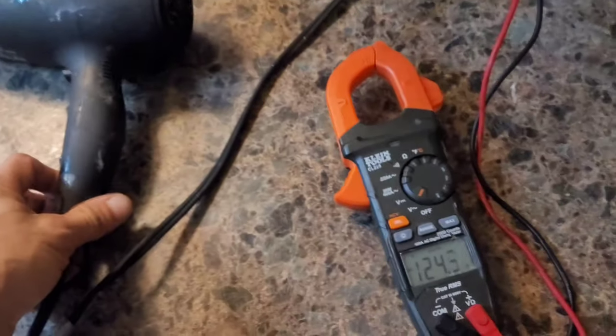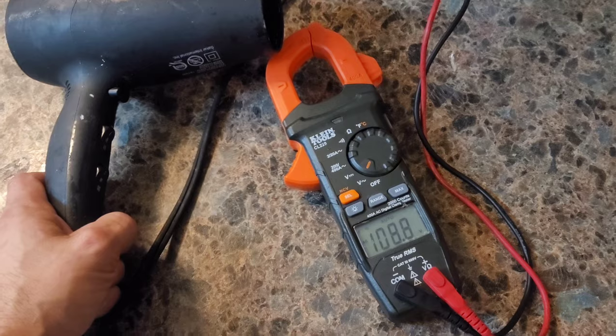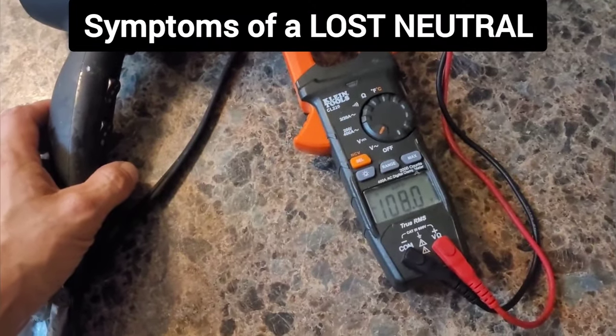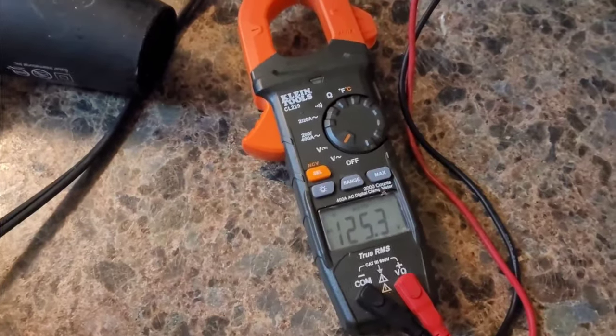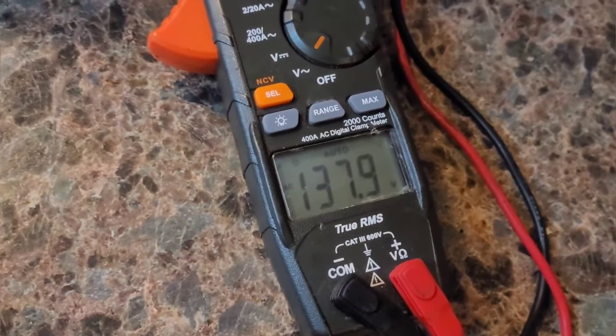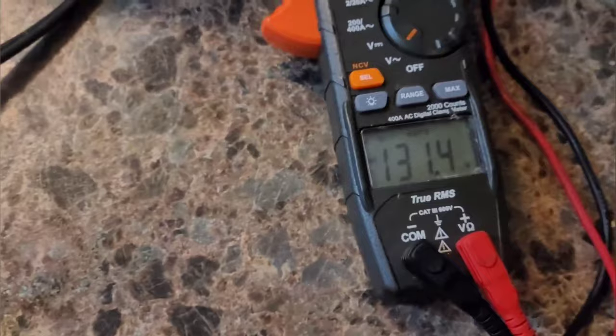This next issue I think is unrelated. Our lights kept flickering and dimming — when the washer was running the lights would flash really badly. You may not be able to tell on video, but when I turn the microwave on you can see that once it gets going we've got a big voltage imbalance.